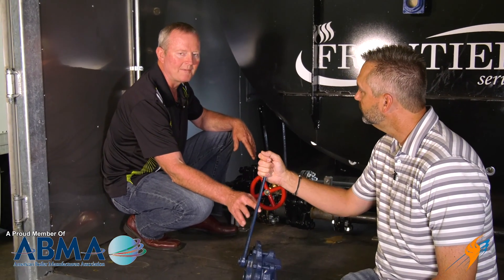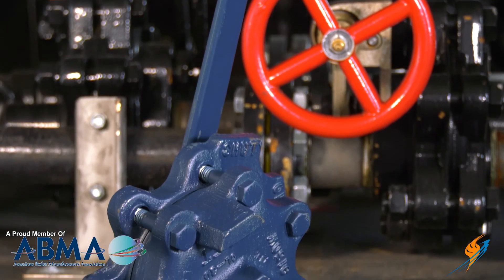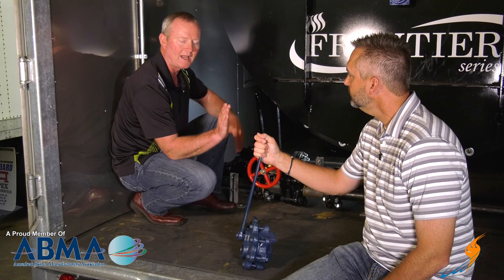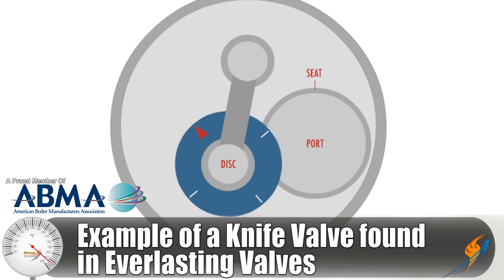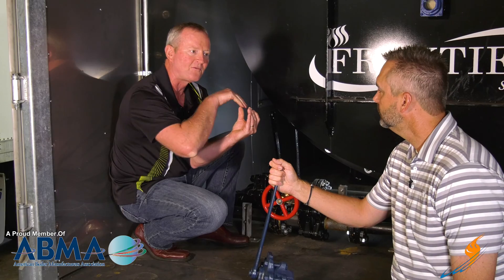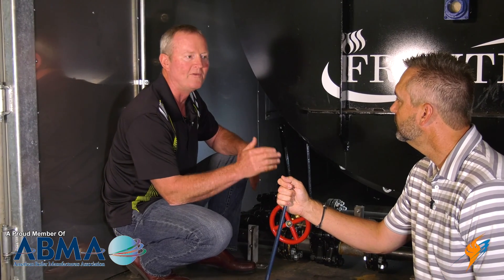The Everlasting is probably the most common valve in the industry. It's been around forever and it's very reliable. It holds up everywhere. This is a knife blade type — you have a pair of sealing flanges, and a knife blade that goes down inside the seal. It's wedge-shaped so it does a really good job of sealing off, and it's self-cleaning when you open it up and flush. It cleans all that stuff out so you don't have a groove full of sediment that won't seal back off. It's a really nice design.